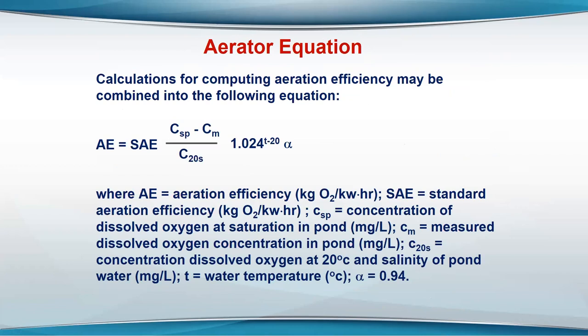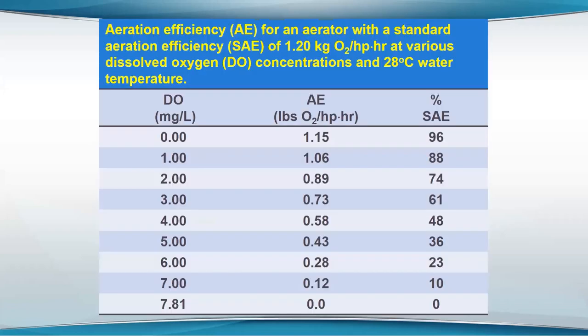There's an equation for calculating how much oxygen the aerator will actually transfer under operating conditions. If the aerator has been rated in a test in clean water to transfer a certain amount — say 1.2 kilograms of oxygen per horsepower hour — at zero dissolved oxygen it would actually transfer about 96% of that value. I noticed a slide error — it should be kilograms of oxygen per horsepower hour; that was just an example.